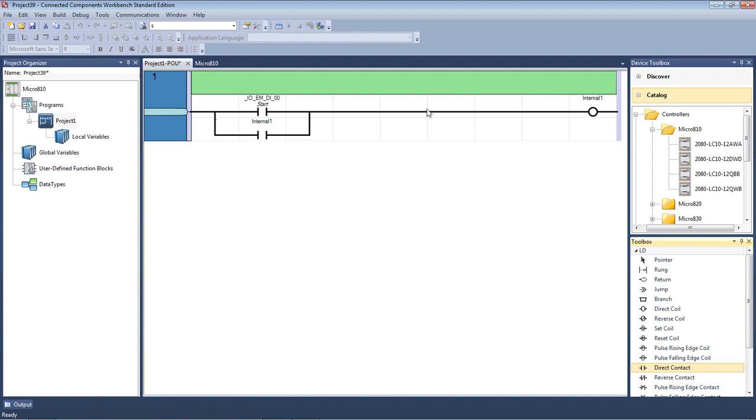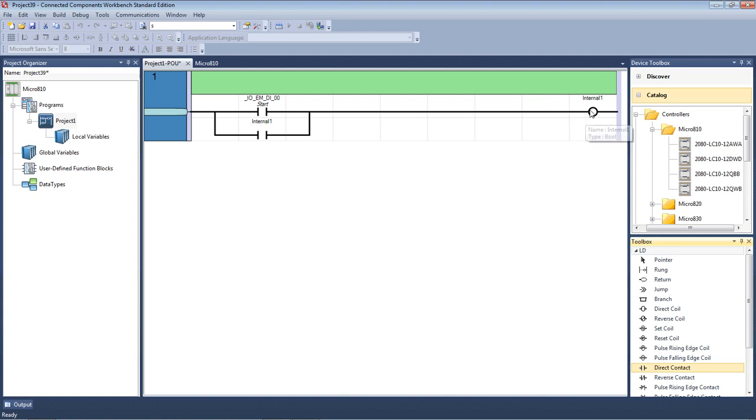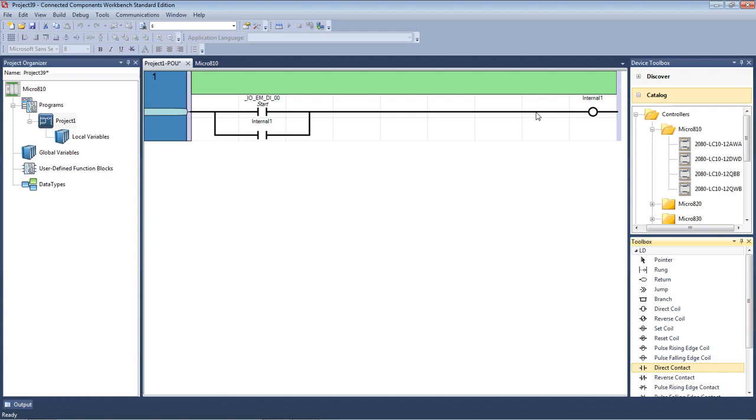Now, the logic here is very similar in terms of our circuit diagrams. So we have all the action elements in this part of the circuit. For the outputs, we only have the one output for any rung. So we can't put outputs in series with each other, as you would do with a circuit diagram, you wouldn't have coils. So you can picture these as the coils of a relay, so they don't go in series. If you need extra logic, you can build a new line below and put a new internal relay in.